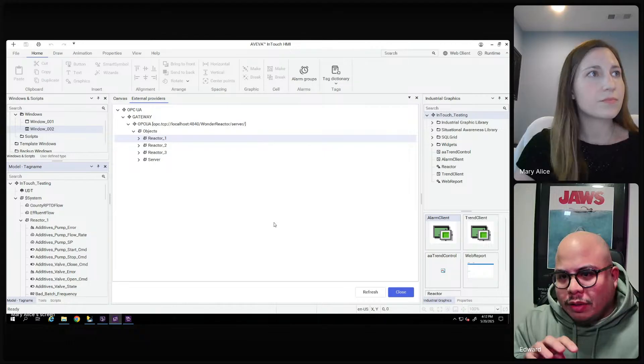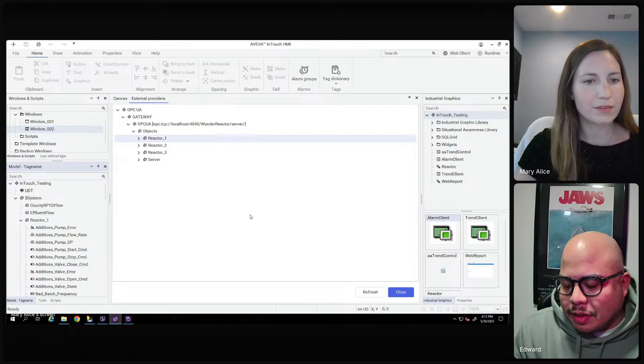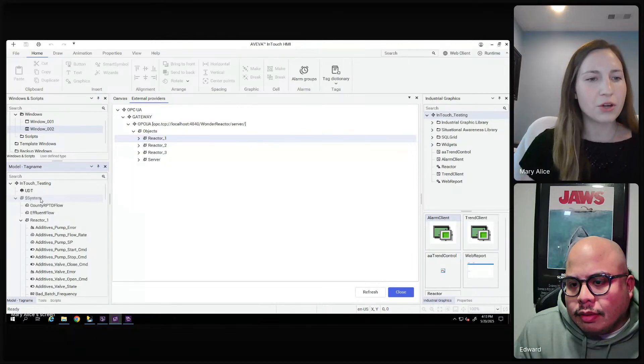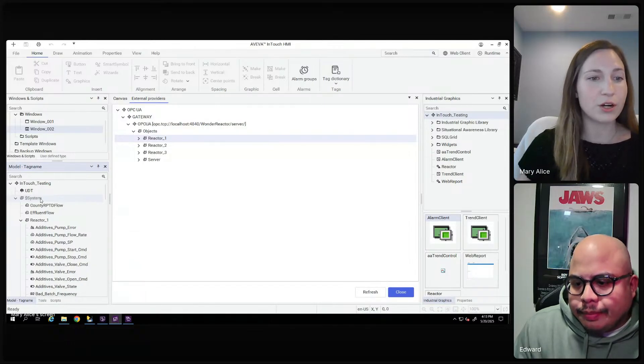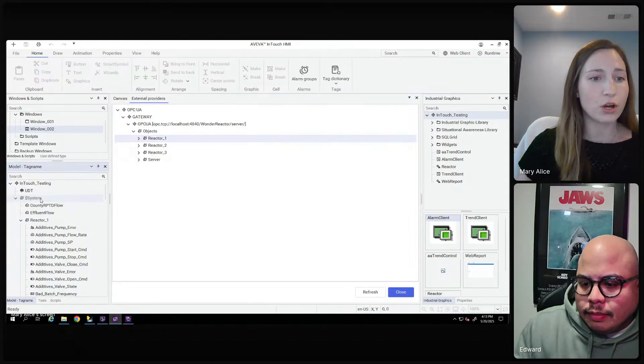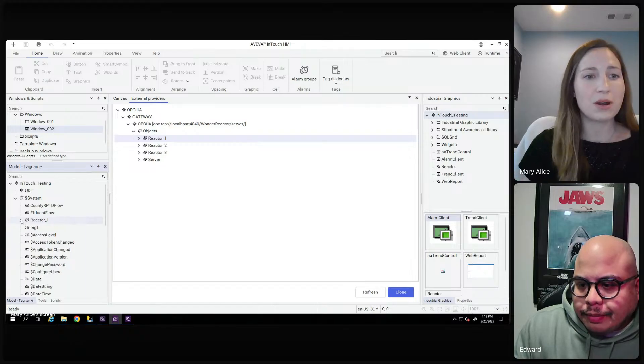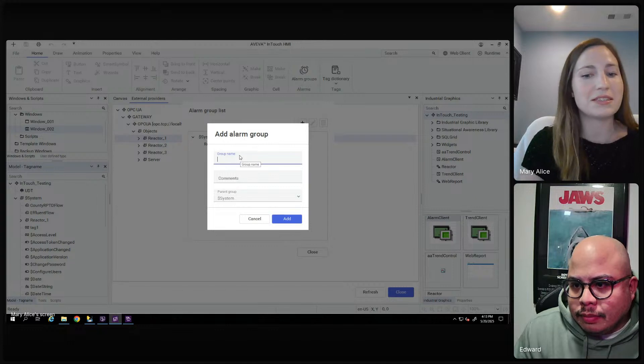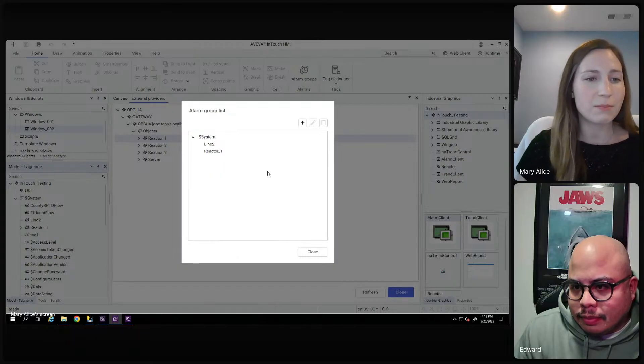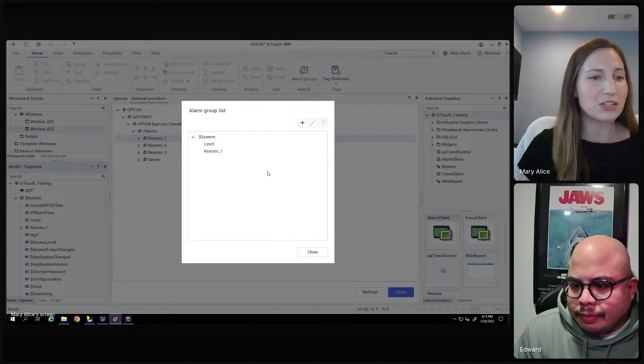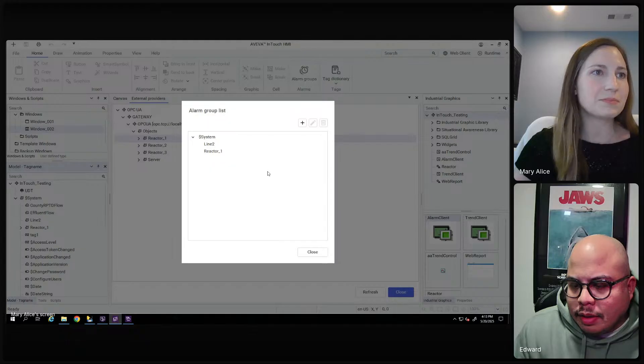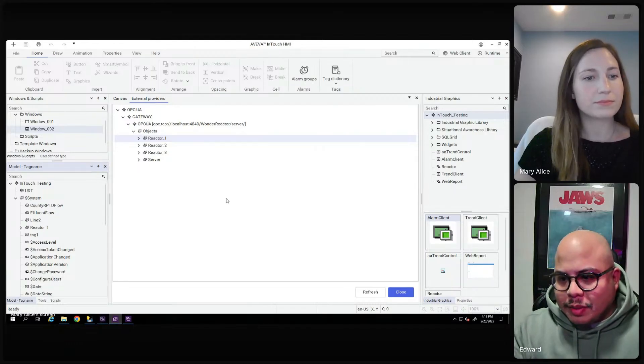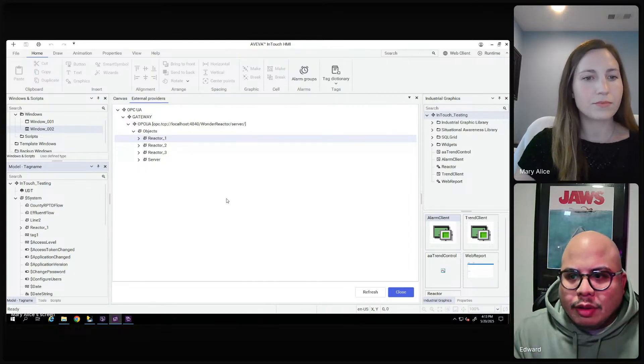I noticed while you were putting things over that the tags went into Dollar Sign System — what does that mean to users? By default in InTouch we have this Dollar Sign System alarm group. Alarm groups are just a way to track and manage the alarms in your InTouch application. I can create my own alarm group — maybe I want to track alarms by dividing out certain areas of the plant. I just come into alarm groups, click to add a new one, name it, and it's part of my application. So if you have an alarm client control on a screen and want to filter results for just Line 2, it's already set up for you.